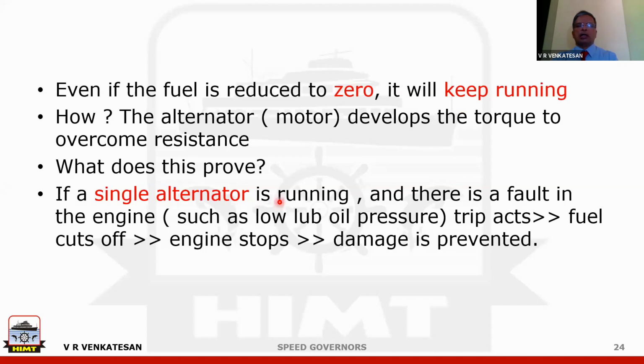Imagine a single alternator running and there is a fault in your engine. The easiest fault to understand is low lube oil pressure. Low lube oil pressure takes place because of a clogged filter or something. The low lube oil trip will activate, fuel will get cut off and the engine will stop. Because of this, damage to the engine will be prevented.